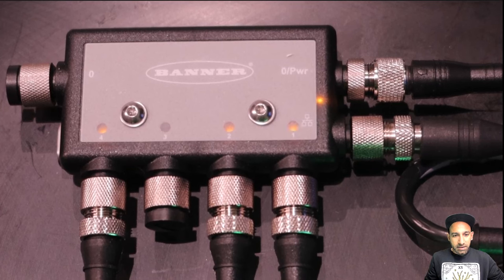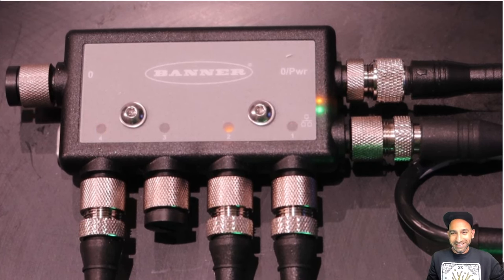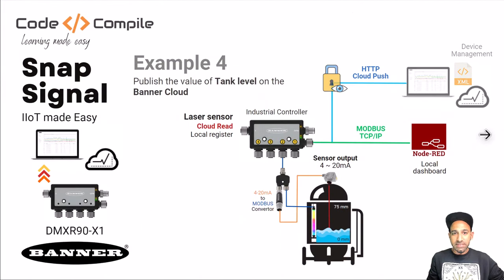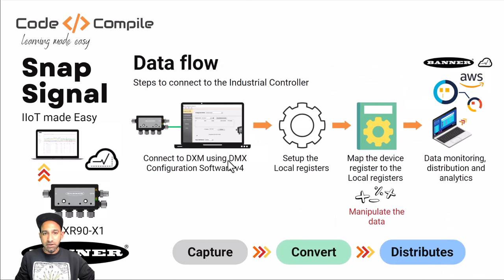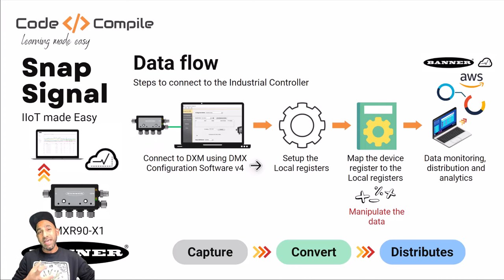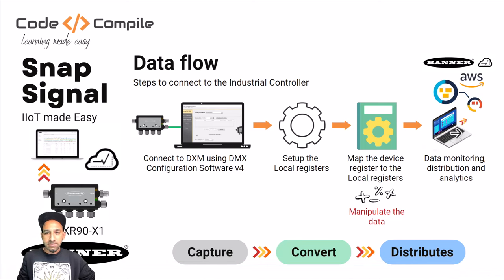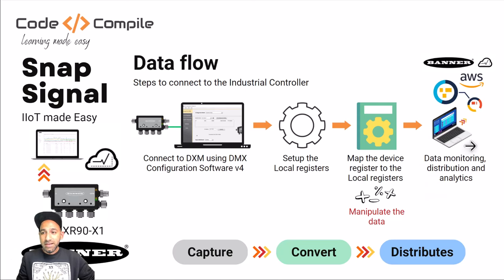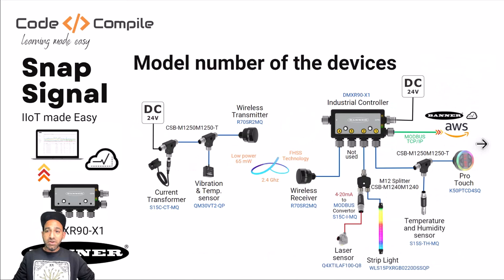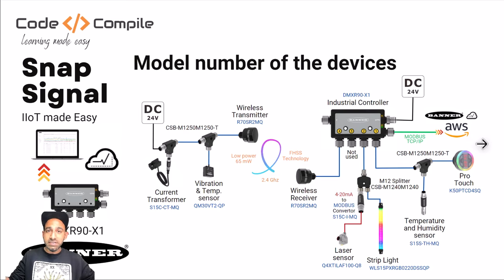To summarize what we did: we connected the DXM controller to the DXM software, set up local registers, captured data from sensors, converted the data using scaling, mapped and manipulated the data, and then sent it to the cloud or to Node-RED using Modbus TCP/IP or HTTP cloud. So the workflow is: capture, convert, distribute — really quick. You can imagine many applications with these sensors and the controller, converting sensor signals to Modbus to easily send to further networks, communication devices, or a data logger.